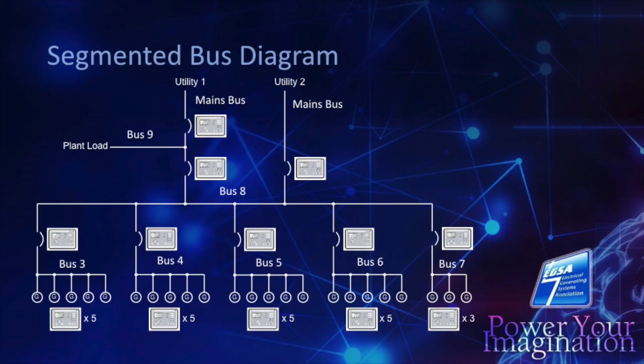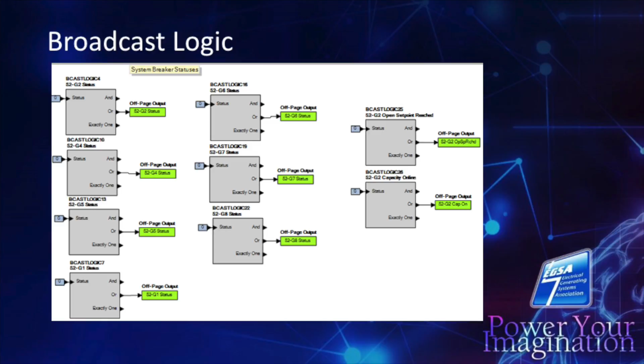And these broadcast logic bits really helped in the design of this, and I know this allowed us to not use interconnections between controllers with a lot of different cables, and it really made it easier. This was another selling point to the switchgear builders and the contractor, that they didn't have to pull a lot of wiring between the controllers, because 3 of the main controllers are all located about 400 feet away from the generators. So it would have been an extremely long run and a lot of cables to do statuses between breakers, which we really need in this system.